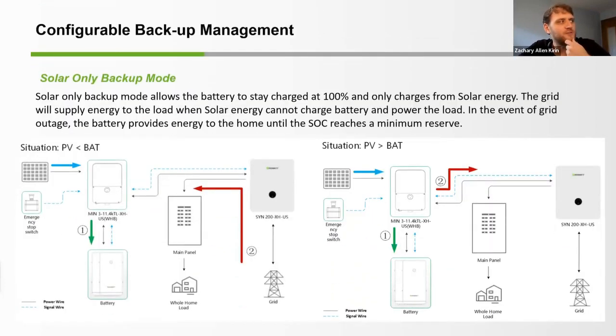We have a couple different modes for solar backup. The one, I would say the more important mode, is something that you might set for customers who have their battery, but they only want to use the battery for backup. This is called solar only backup mode. Solar only backup allows the battery to stay charged at 100% and only charges from solar energy. The grid will supply energy to the load when the solar energy cannot charge the battery and power the load at the same time. In the event of a grid outage, the battery provides energy to the home until the state of charge reaches a minimum reserve. So this is one option utilized for keeping the battery ready to go in the case of a grid outage.